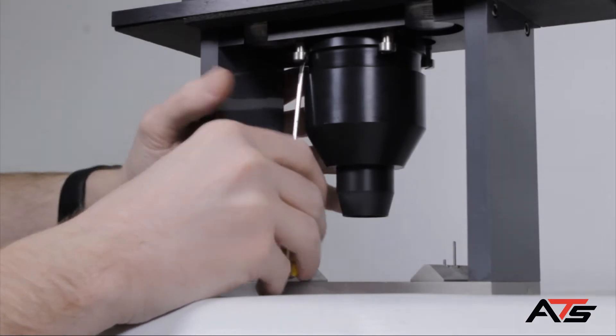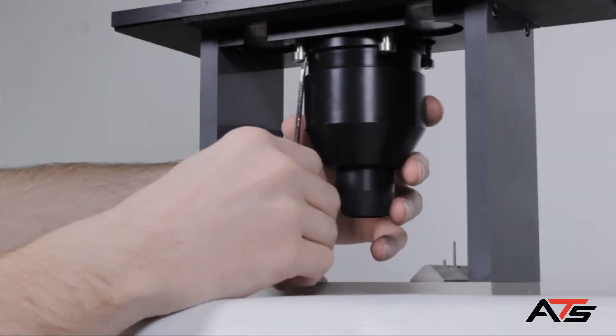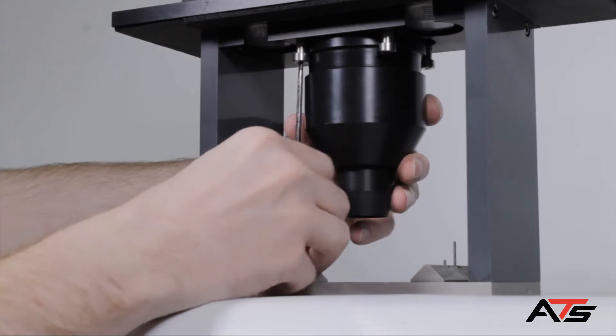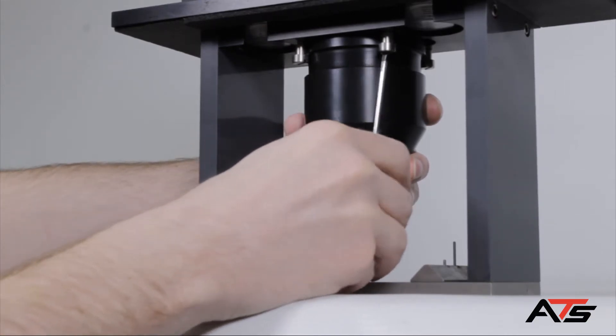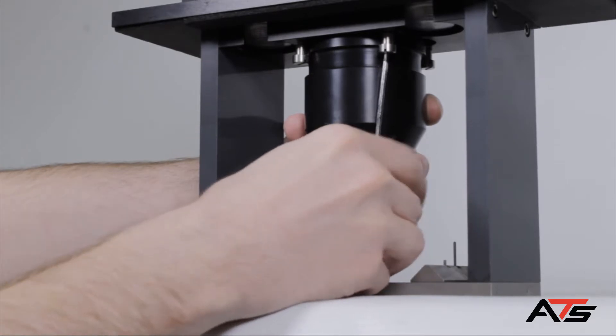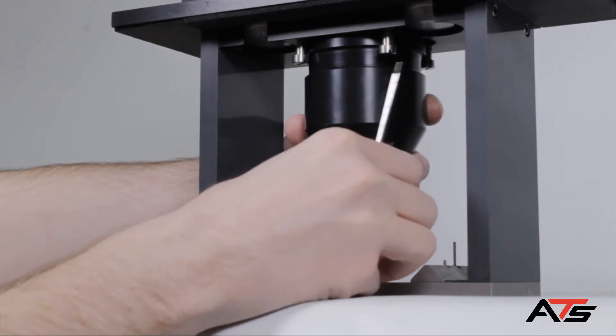There are four screws securing the shroud to the load frame. Remove the front two screws and loosen the back two screws to remove the shroud from the frame.